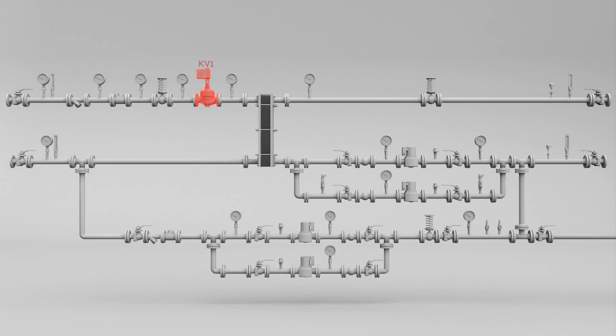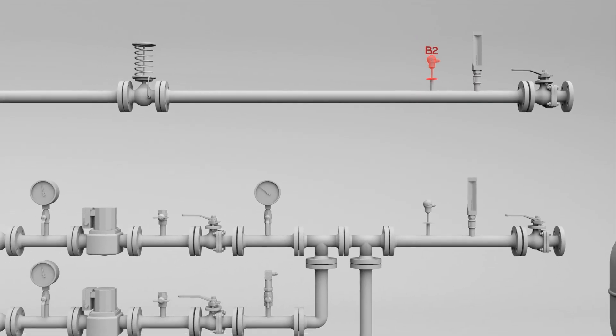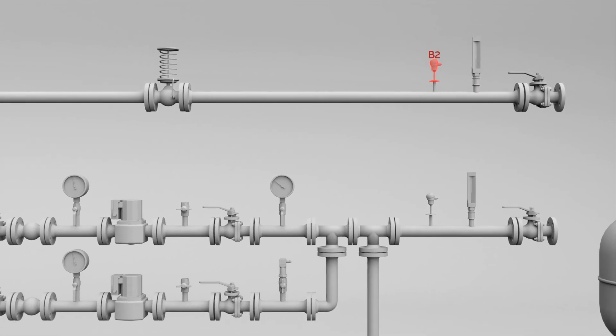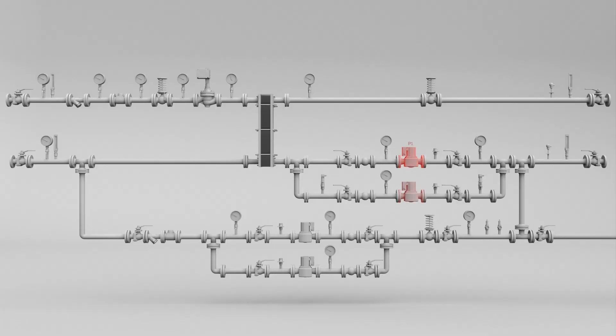First, which set points are we talking about? There is a control loop of valve KV1, where the process value comes from supply water temperature. There is also pumps 1 and 2 control loop, where the process value comes from return water temperature. As you can see, both control loops must get set points somewhere.